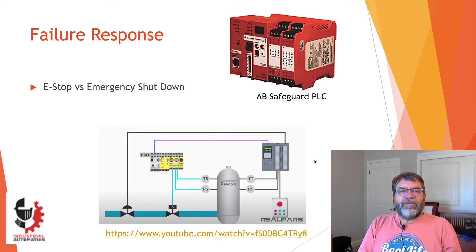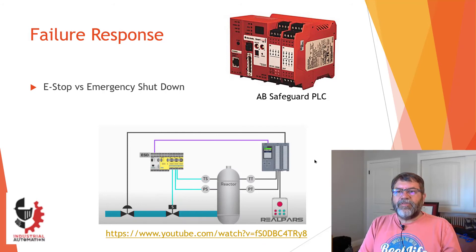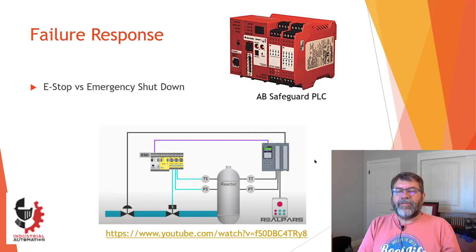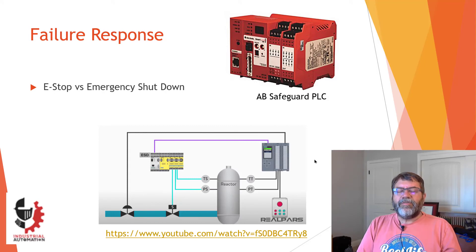The last one is failure response — something we haven't talked about much before. E-stops have been used on machines for many, many years, and typically an e-stop will just shut a PLC down. You hit the e-stop, the PLC goes dead, everything stops, and that was thought to be a good safe condition.